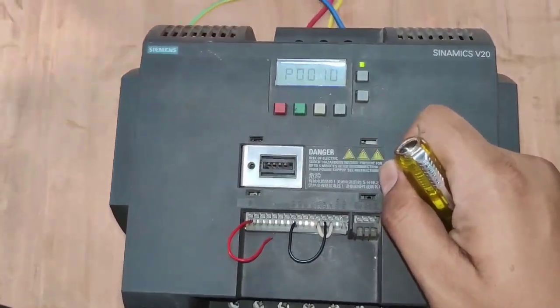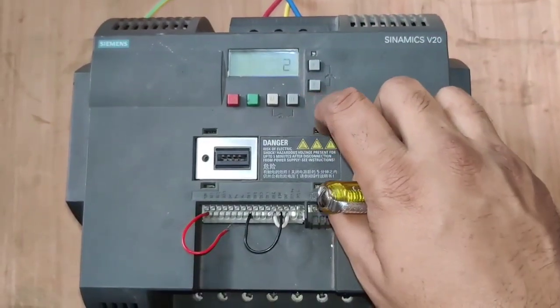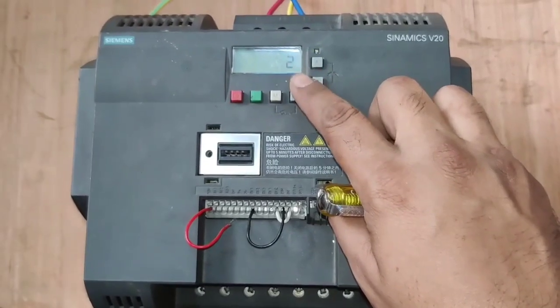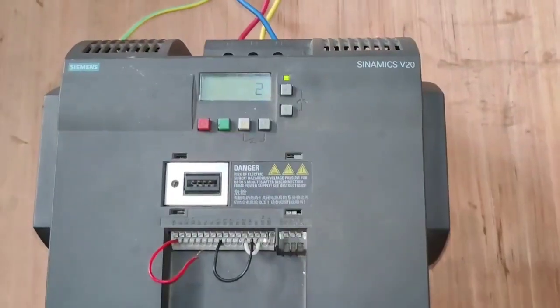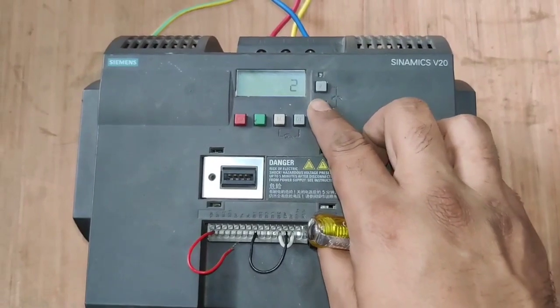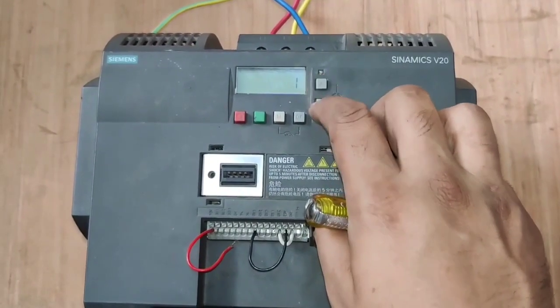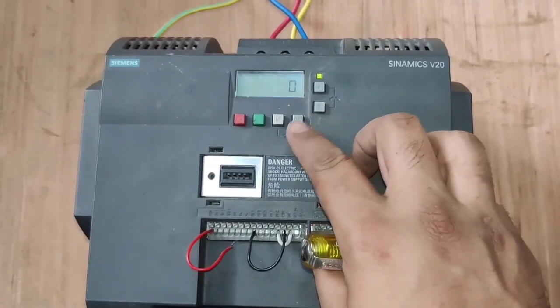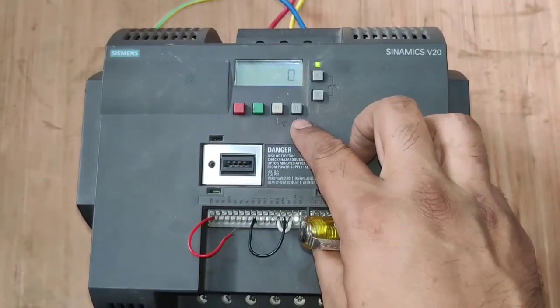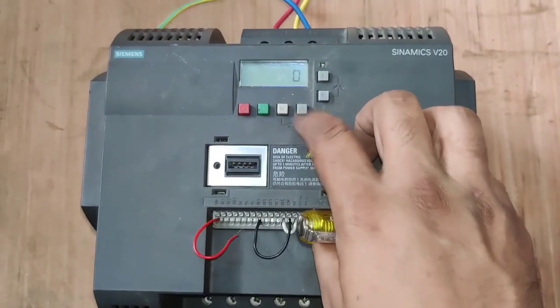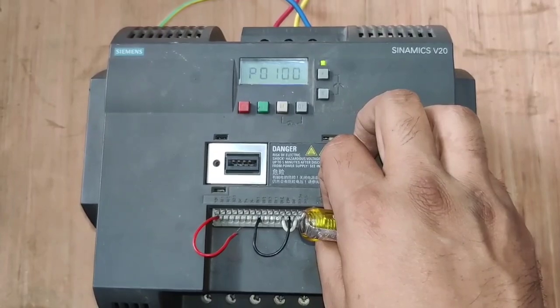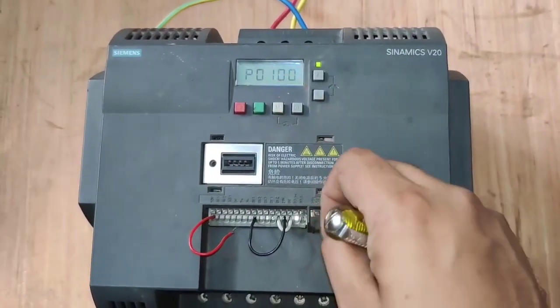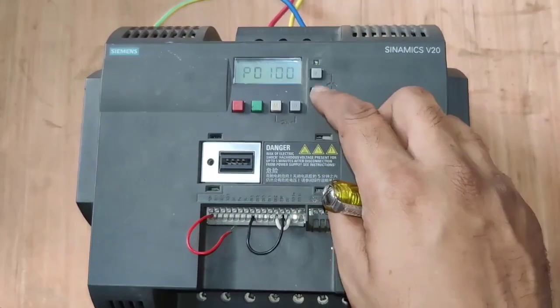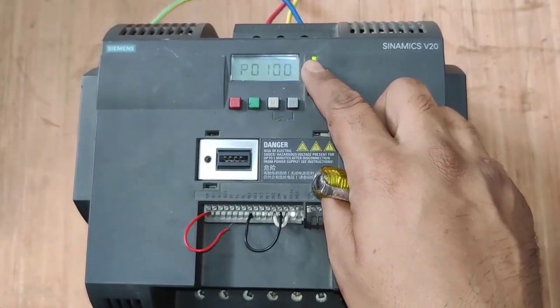Okay, we set 1 for parameter commissioning. Next parameter is P100. In P100 we can set the frequency according to which country you use your drive. If you set 0, that means this drive is programmed for Euro frequency, 50 Hz. If you set 1, that means the drive is programmed for North America frequency, 60 Hz. Now the drive is programmed for Euro frequency, 50 Hz.